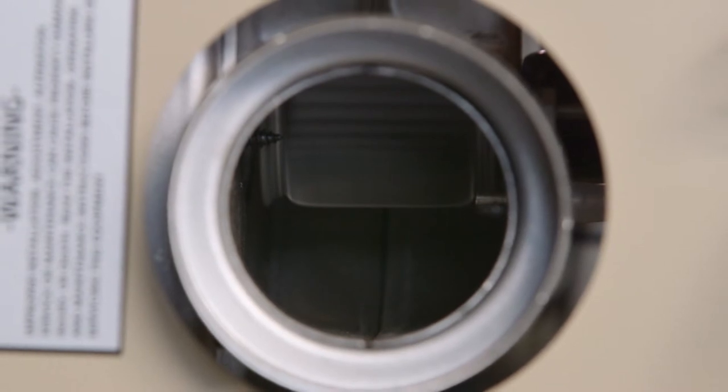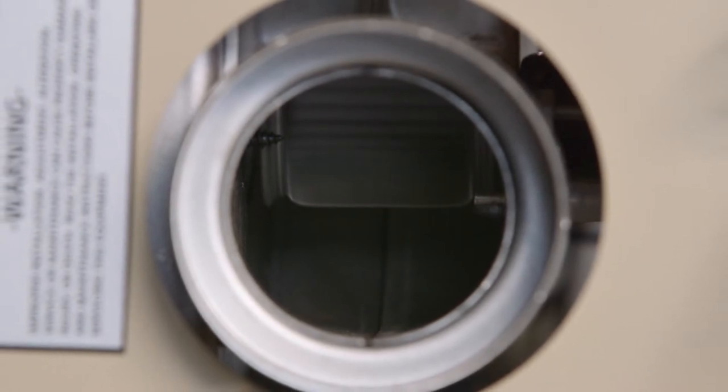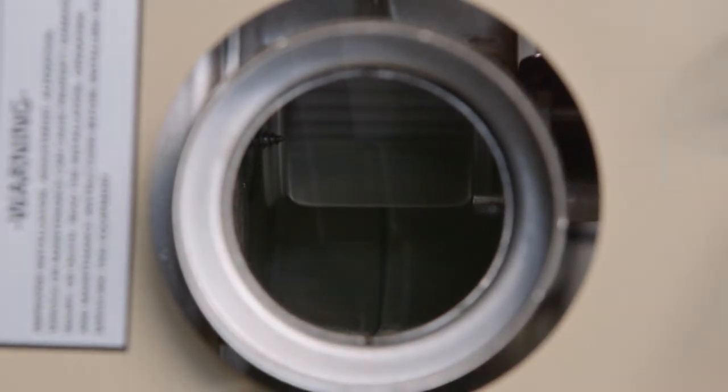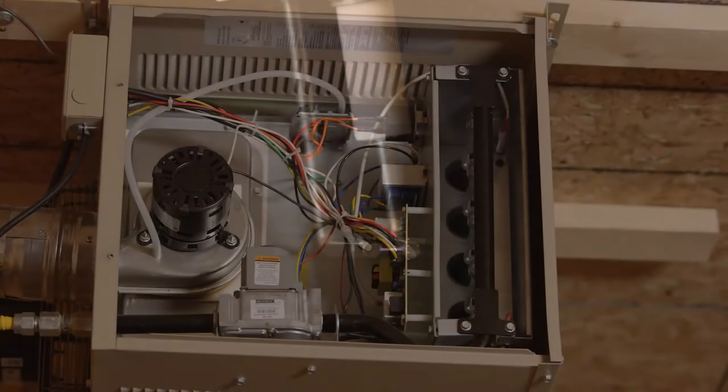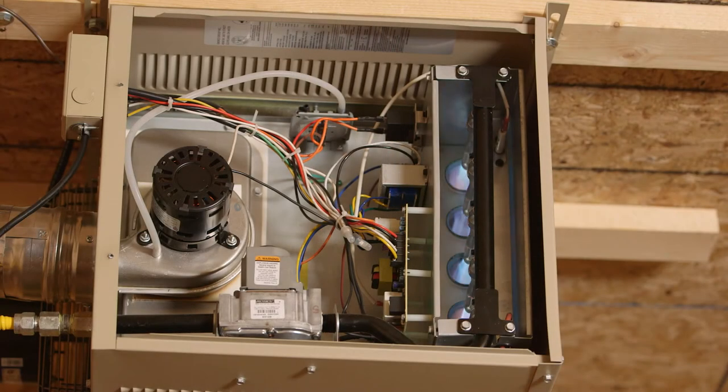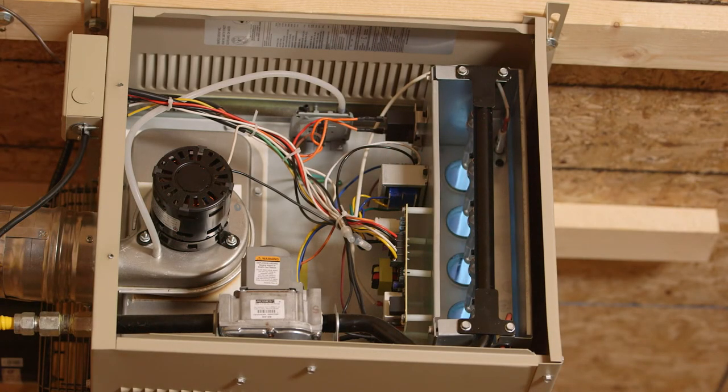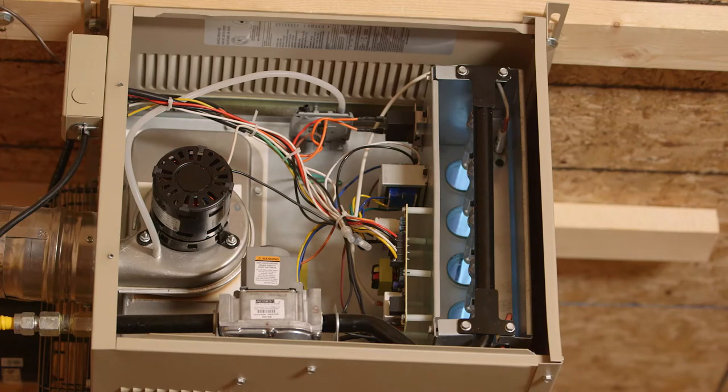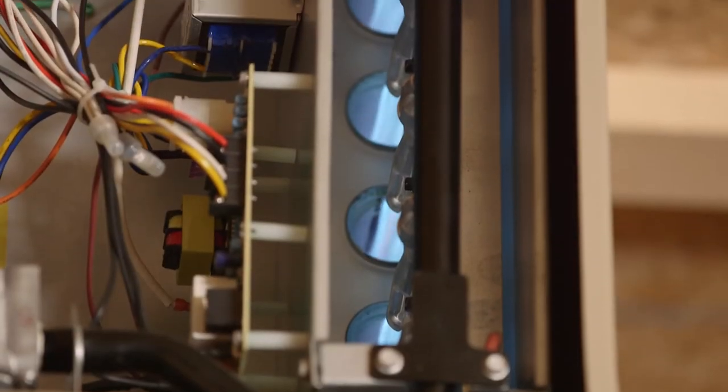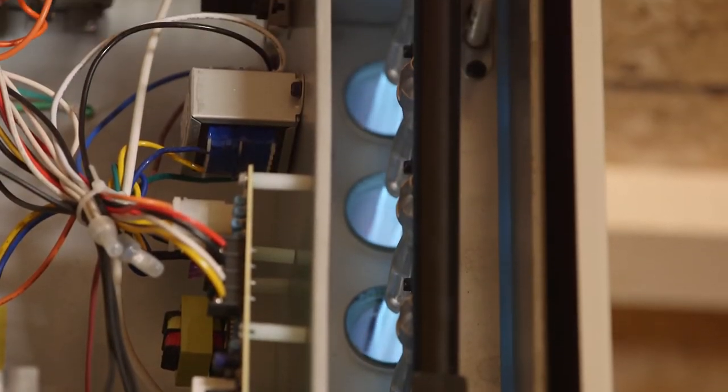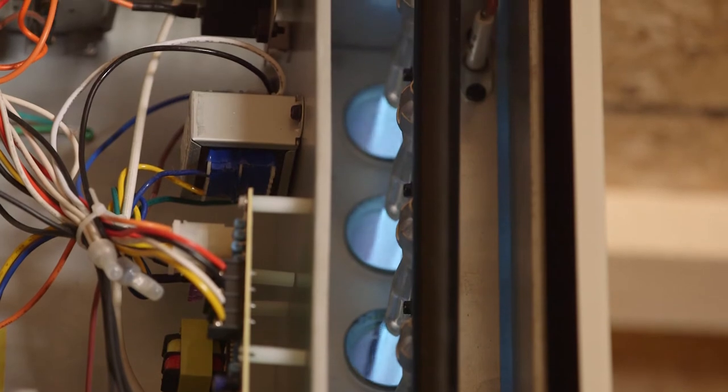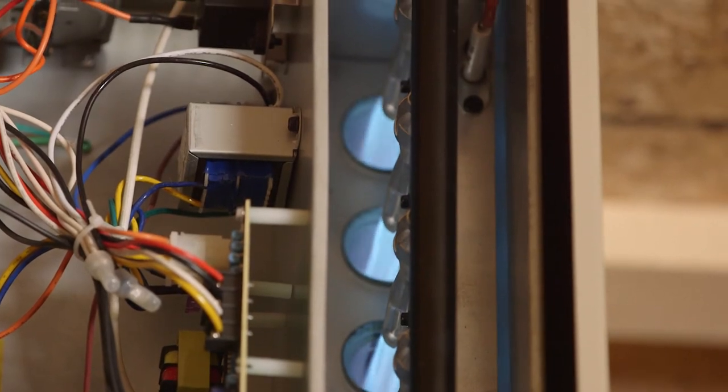After 30 seconds, with the induced draft motor still running, the electrodes start sparking. Just after the electrode starts sparking, the gas valve will open with a loud click. All burners must then light. The electrode keeps sparking for 10 seconds. If all the burners are lit, a flame sensor signals the control board to stop sparking.